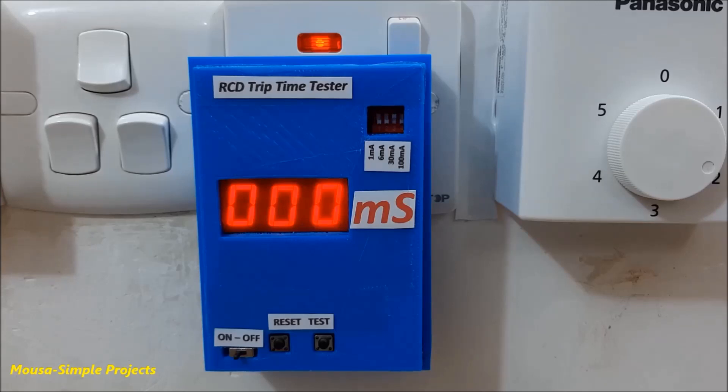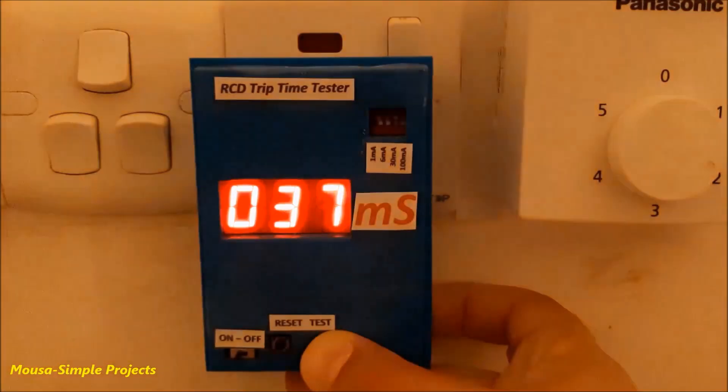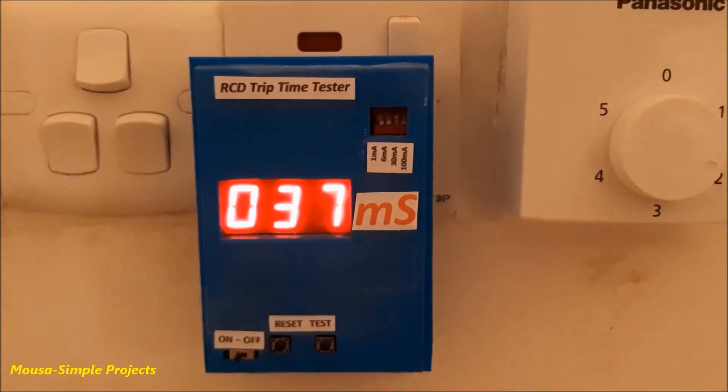I switched on this circuit, connected it to the mains voltage, and selected 30 mA of leakage current because my RCD type is 30 mA. By pushing the test button, the RCD trips and this circuit calculates the trip time.